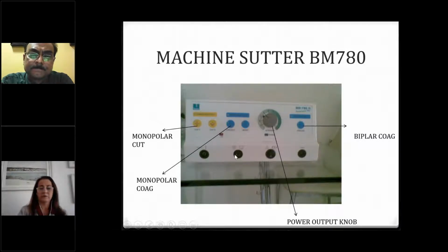This is the ground electrode, or the earthing plate, which is usually put close to the operating surface. Usually we put it under the shoulder, since we function mainly in the head and neck area. And this is the other socket for cutting mode electrodes more than coagulation mode. But mainly we tend to use this and this for the bipolar coagulation mode.